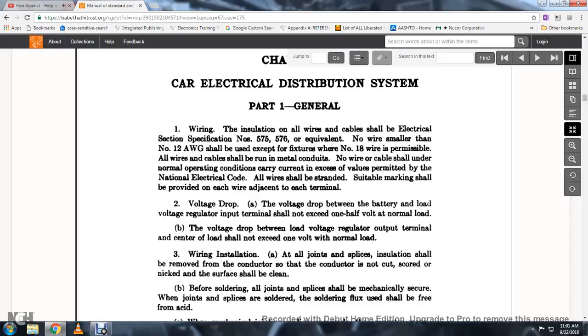Voltage Drop: The voltage drop between the battery and the load voltage regulator input terminal shall not exceed one half volt at normal load. The voltage drop between the load voltage regulator output terminal and center of the load shall not exceed one volt with normal load.